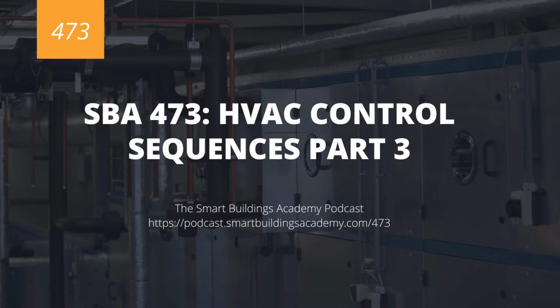And the reason why is, oftentimes when folks are new to this field, they'll say, oh, Economizer, it's 65 degrees outside, I'm going to control with the Economizer. It's great, awesome, free cooling. And then they don't look at like 65 degrees, 90% humidity. I know those are some crazy wonky numbers, but what you have to realize is as temperature increases, the effect of relative humidity is massive.